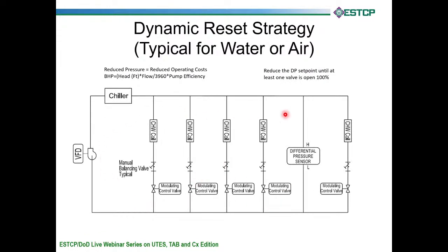This is also a system that you would typically see used in geothermal. This is a chilled water system. This could be a modular chiller that uses groundwater or water from your GHX out here from your BTES or your ATES. In this case, like I said, we have a chilled water loop. We have chilled water coils here. We have modulating control valves instead of two-position control valves, because we want to be able to vary the capacity through the chilled water coil.